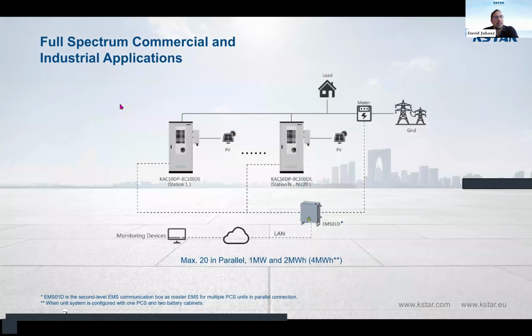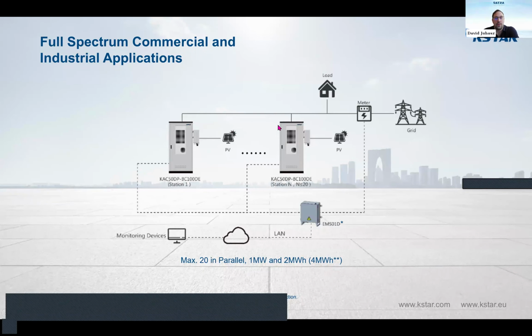So regarding this application, the maximum number of inverters in parallel is 20 pieces, and it can go up to 1 megawatt charge or discharge power. And regarding the storage capacity, it can go up to 2 megawatt hour or 4 megawatt hour, but for the 4 megawatt hour solution, you have to double only the cabinets.